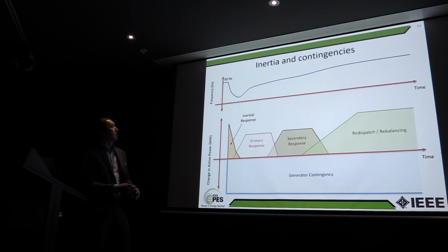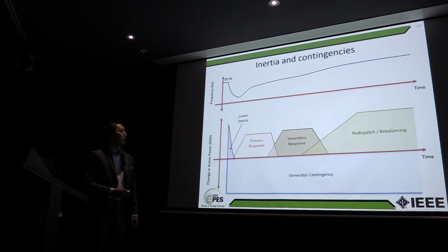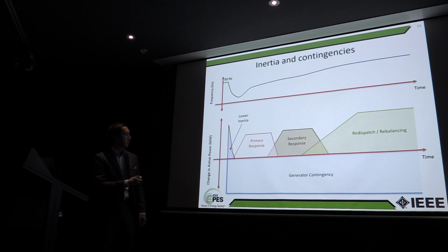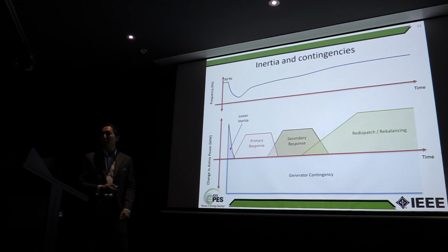So we go back to this idea of inertia and contingencies. Now, what happens if we had a lower inertia? If we have a lower inertia, we actually have less energy under the curve here. So what happens is we end up with a higher RoCoF, as we described. We also end up with a lower nadir in the system.